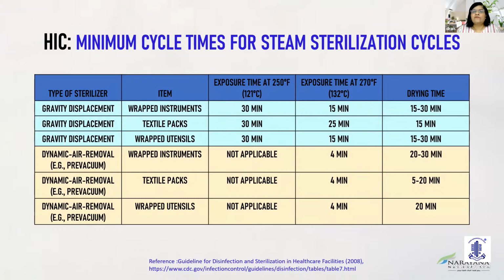Now, what is the minimum cycle time for steam sterilization cycles? According to the guideline for disinfection and sterilization in healthcare facilities from CDC, this is the guideline which they follow. It depends on machine to machine, eventually at the manufacturer's discretion and guidelines. But basically, a gravity displacement sterilizer with wrapped instruments, textile packs, and wrapped utensils will take an exposure time of around 30 minutes at 121 degrees centigrade. About 15 minutes for wrapped and 25 minutes for textile, and wrapped instruments will have 15 minutes. Drying time will be somewhere around 15 to 30 minutes for the gravity type displacement sterilizer.